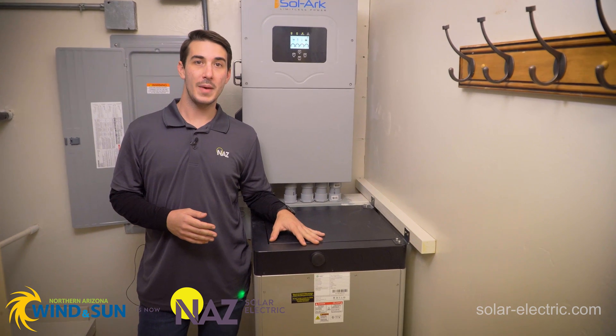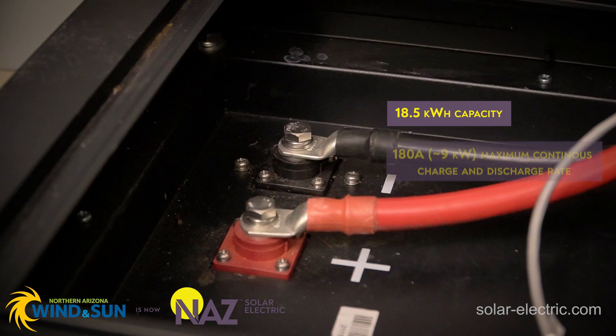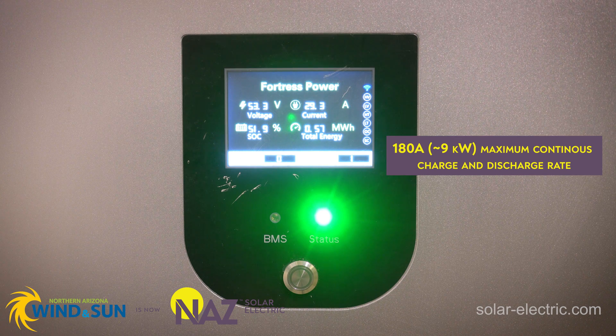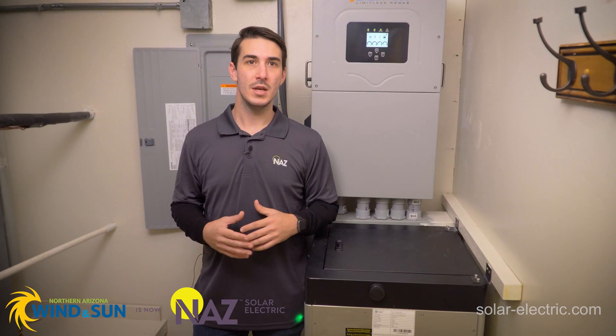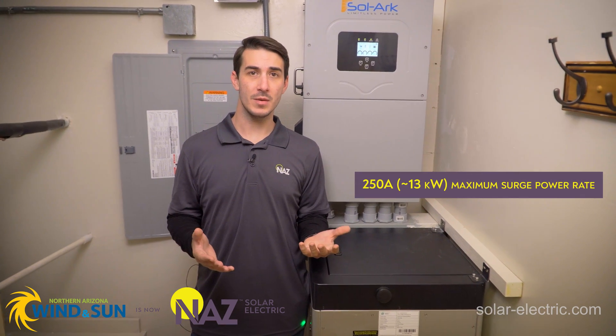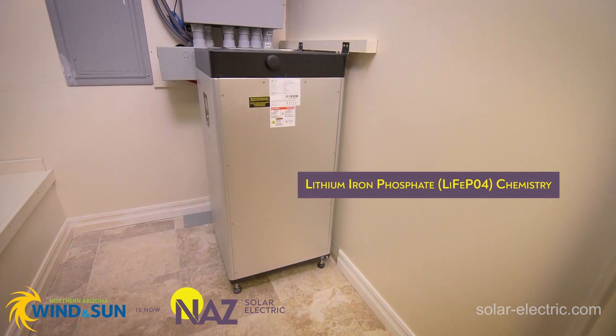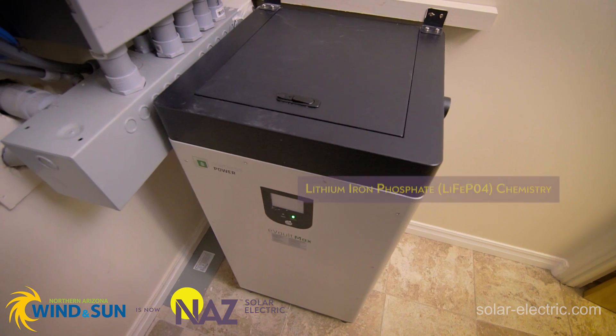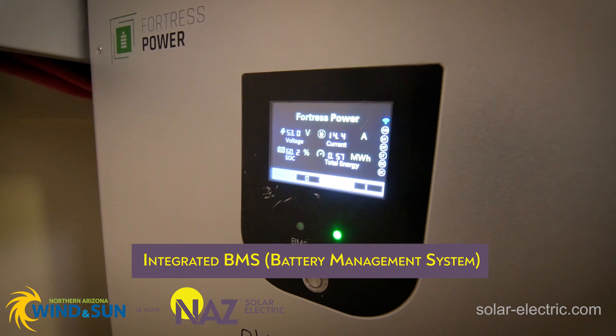The eVault Max battery from Fortress is rated for 18.5 kilowatt hours of total storage. It can do continuous charging and discharging at about 180 amps, which is around 9 kilowatts. And then it has a surge up to 250 amps, which is somewhere between 12 and 13 kilowatts it can provide as a maximum. This is a lithium iron phosphate battery, so non-volatile chemistry, maintenance-free, totally sealed. The BMS battery management system is fully integrated into the battery.